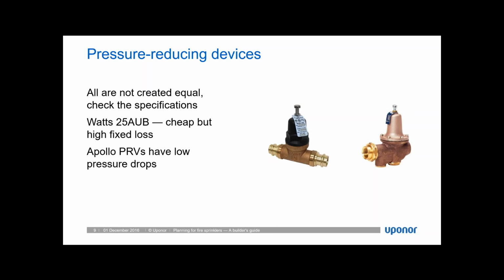Now, like I state here, Apollo pressure reducing valves have low pressure drops, and if they're available in your area, they are definitely a good option. Now, I'm not advocating for any particular manufacturer of pressure reducing valves, and I'm definitely not trying to point out anything negative about Watts, because Watts also has other models of pressure reducing valves that are going to be much more ideal for fire sprinkler systems. I'm just trying to point out that it's important to pay attention to what is being installed on the system.